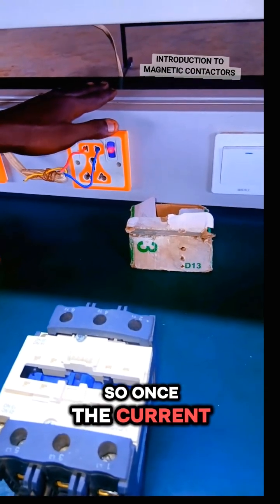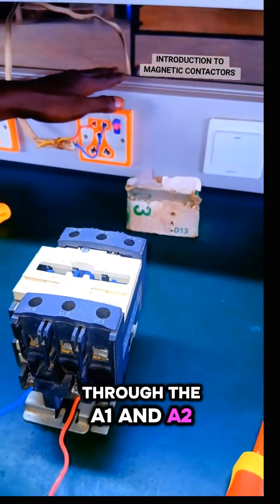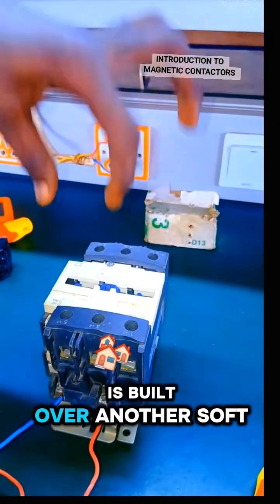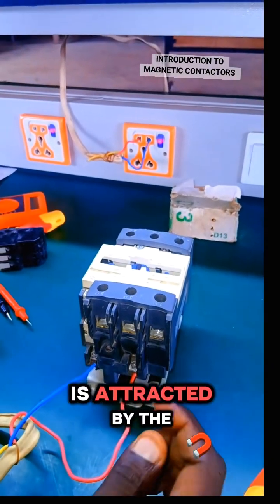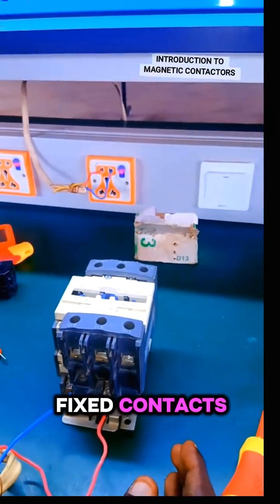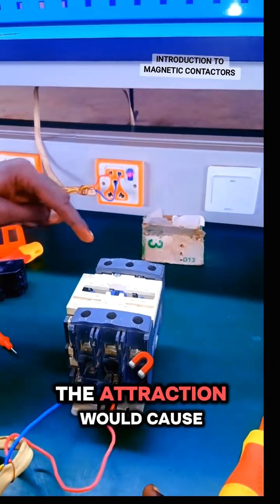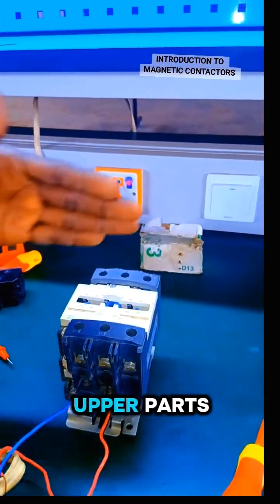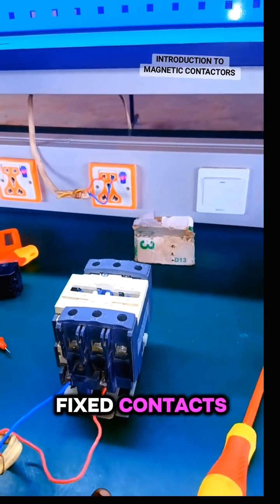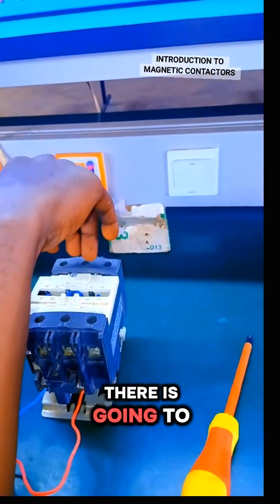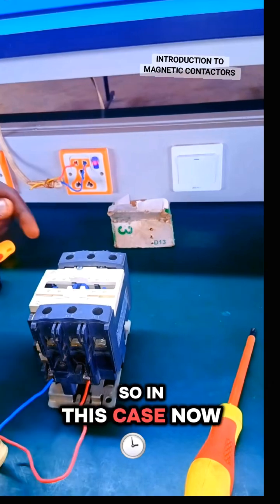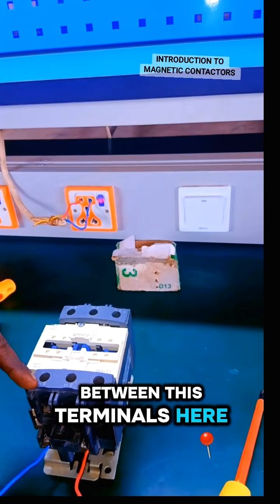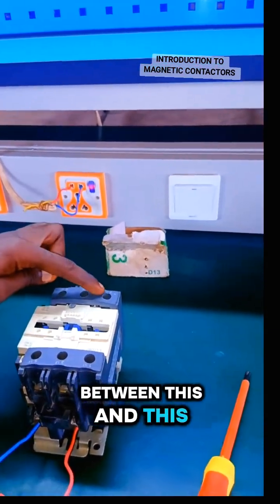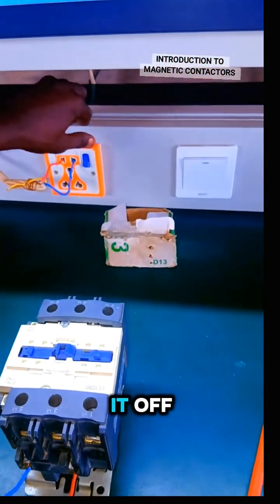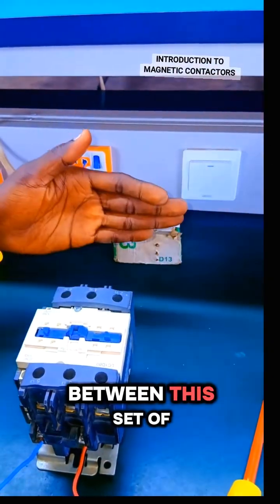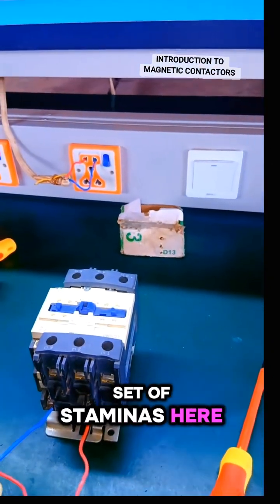Once the current gets to the coil through the A1 and A2, the movable contact, which is built over another soft iron core, is attracted by the soft iron core of the fixed contact. When they become attracted, the attraction will cause a link between the contact at the upper part and the contact at the lower part in the fixed contact. So whatever supply you put here, there is going to be continuity for them at the other side. So in this case now, there is continuity between this terminal here and this terminal here, and between this and this. And the moment I switch it off, there is no continuity again between this set of terminals and this set of terminals. Hope that is clearly understood.